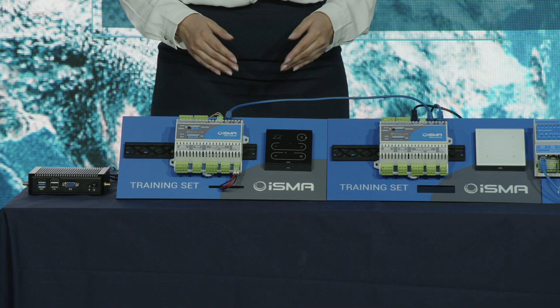But I can see the second UAC 18 is not powered up. Why is that? To show you that the fail-safe protection in the Ethernet ports is working. Even though this controller is not powered up, the communication still goes further to the next device, so even with no power supply, the communication signal goes through this switch.